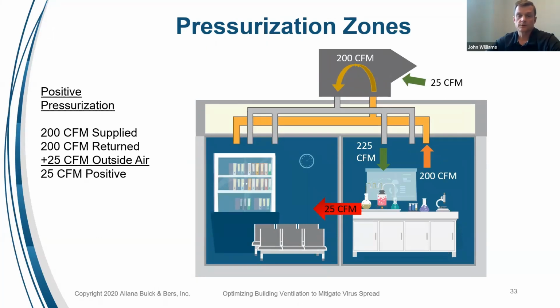However, if we introduce 25 CFM of outside air, and once again, this is the airflow in the air handlers just for the room on the right, we now supply 225 CFM of air to the room, but we're only returning 200. So now we have a positive pressure of 25 CFM. And this is going to result in airborne particles being pushed from our room on the right to the room on the left. So if we want to contain that, how do we do that?